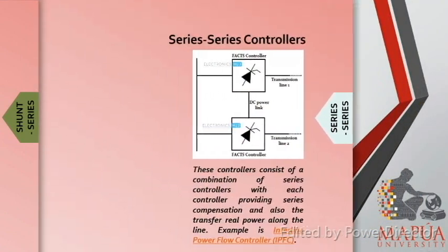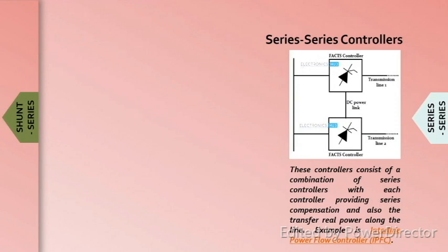The third type is the combined series controllers. These controllers consist of a combination of series controllers, with each controller providing series compensation and also the transfer of real power along the line. Example of this type of controller is interline power flow controller or IPFC, which is widely used in managing the power flow of multi-line transmission system.